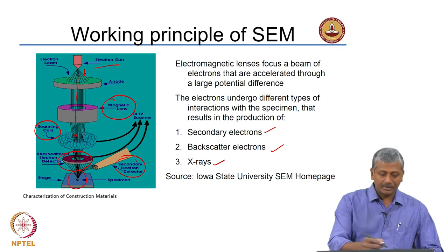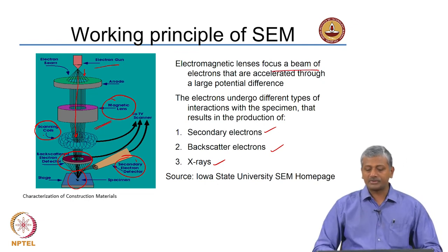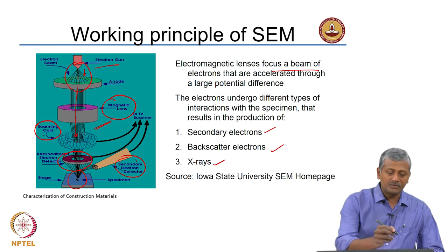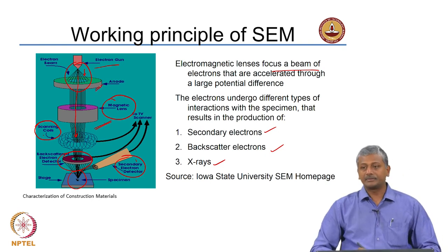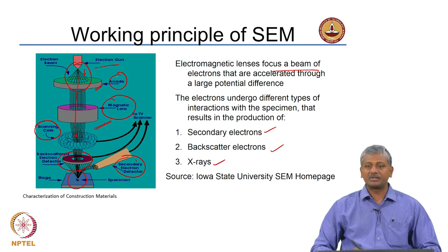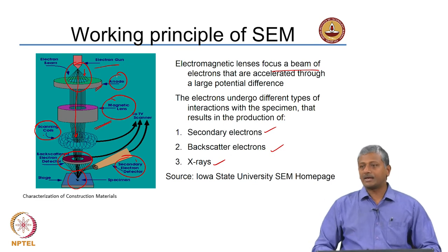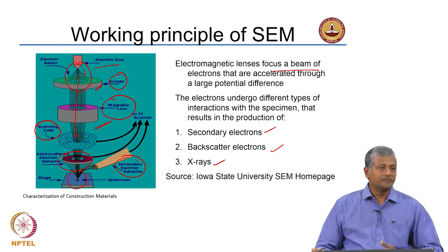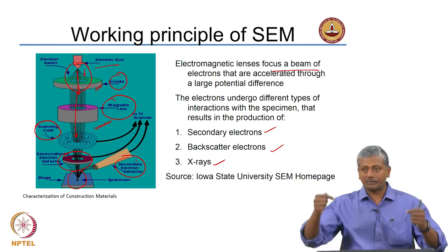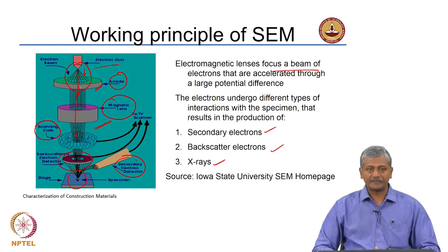The electromagnetic lens system focuses a beam of electrons accelerated through a large potential difference between the electron gun (cathode) and a cap-type anode. The anode is positively charged, so electrons move toward it, and the potential difference increases their velocity. The electrons then move very fast through the anode and down the optic axis, controlled by magnetic lenses to ensure they travel the central path directly to the top of the specimen.